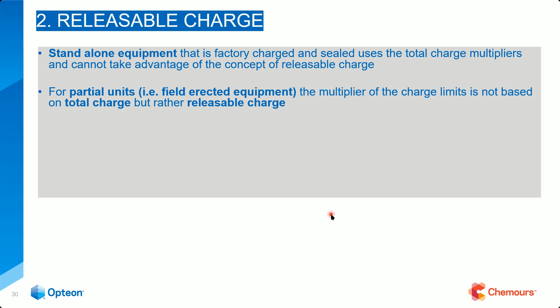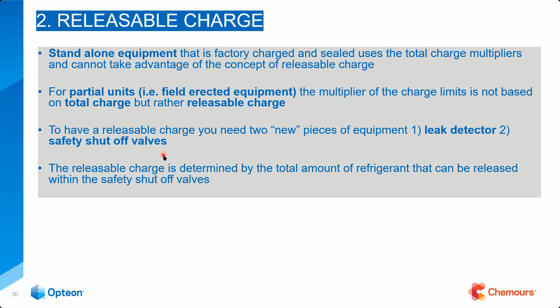To have a releasable charge, you need two new pieces as part of that equipment. You need some type of leak detection built into the system, and then some type of safety shutoffs, whether that be a solenoid valve or a check valve or something like that. The releasable charge is determined by the total amount of refrigerant that can be released within the safety shutoff valves. That's going to be based on volume in cubic feet and different factors.